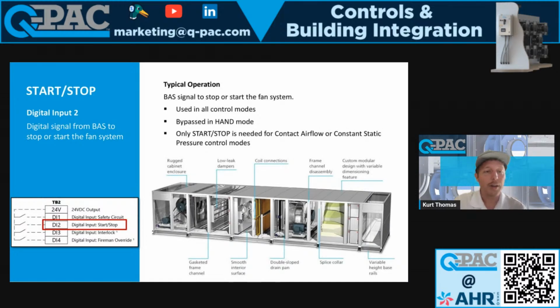All right, start, stop. So digital input 2. This is just a binary signal from your building automation system saying, hey, I want you to run. So there are 2 things you need from, hey, Frank, I see your question. I'll get to BACnet pretty shortly. So there are 2 things we need from your building automation system. We need a speed control, and we need a start signal.